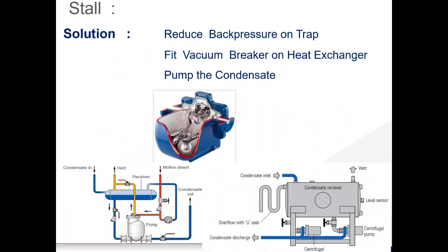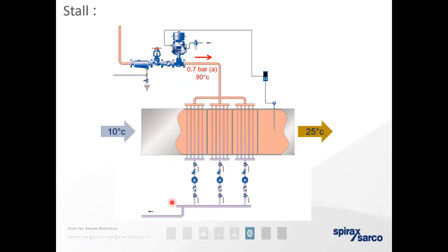Sorry, I just want to touch back on that because I feel like I should clear something up. The reason why you're getting stall here is this control valve closing. You have the collapsing of steam along this line here, which creates a vacuum. So the pressure across the trap becomes close to 0 on this side. You have a back pressure in your condensate line, say it's around 2 or 3 bar. So the trap can no longer pass condensate through the trap and into the condensate line. That's what gives you stall conditions, mostly caused by the closing of this control valve, or not enough drop between your trap and your coils.